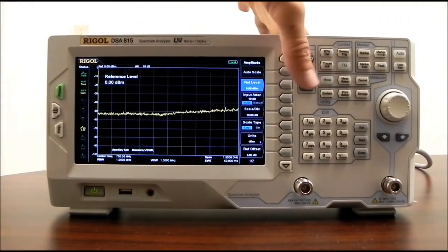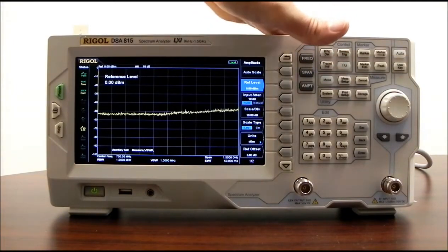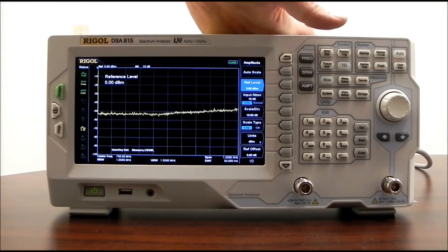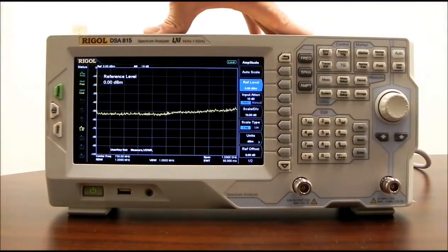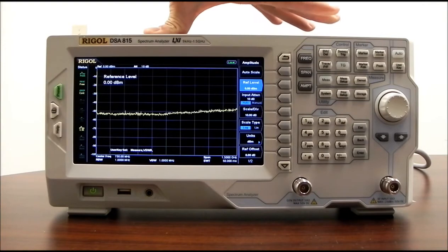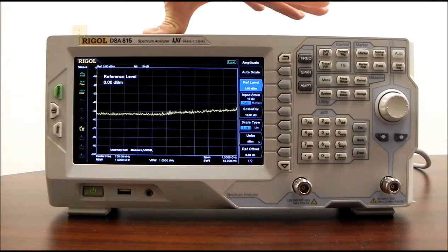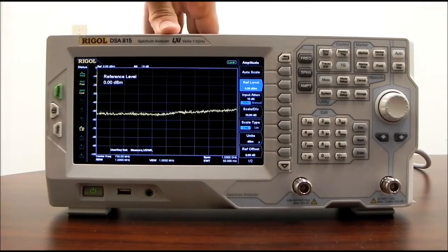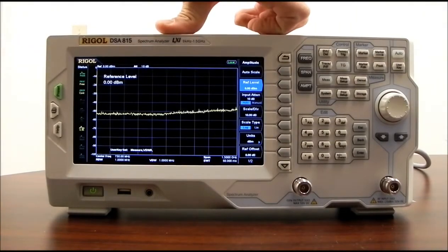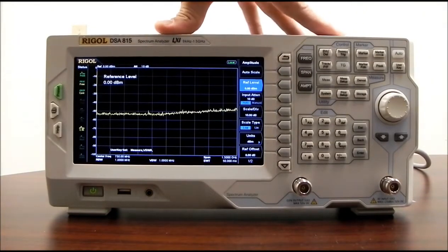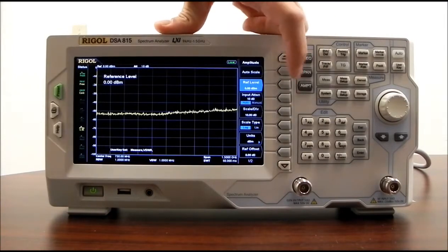And then input attenuator. The DSA815 has an input attenuator that, in factory defaults, automatically comes up as 10 dB. The idea is that we're going to attenuate that input just slightly, and it helps to protect the sensitive circuitry just in case you have any transients that may be discharged while you're connecting, or if you have a source connected that you're not entirely sure what the value is going to be. A good idea is to put in a level of attenuation in order to protect that front end. Generally leave that on auto.